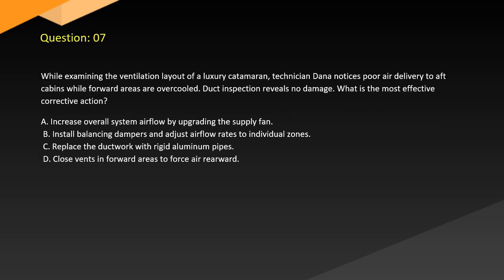Question 7. While examining the ventilation layout of a luxury catamaran, technician Dana notices poor air delivery to aft cabins while forward areas are overcooled. Duct inspection reveals no damage. What is the most effective corrective action? A. Increase overall system airflow by upgrading the supply fan. B. Install balancing dampers and adjust airflow rates to individual zones. C. Replace the ductwork with rigid aluminum pipes. D. Close vents in forward areas to force air rearward.